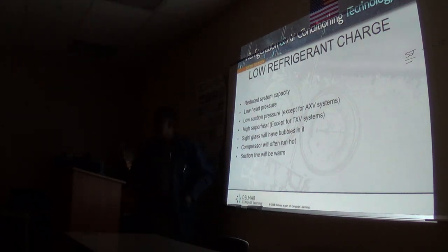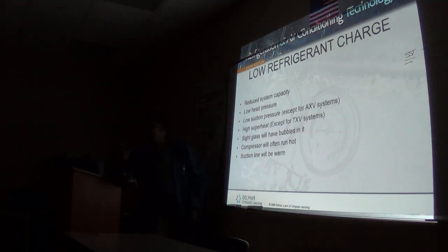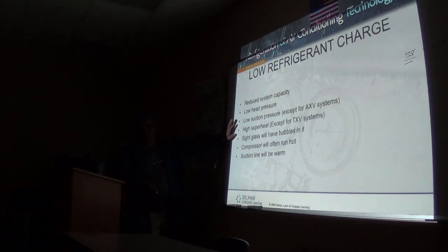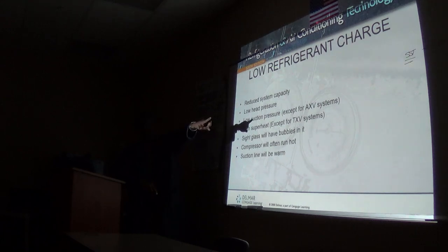So he's low on refrigerant then, right? Yeah, if all around your pressures are low, you're low on refrigerant. I have to bring him more Saturday. And of course you will have high superheat when you get low charge. Just remember that. With a negative 10, you get excessively high superheat. Subcooling is non-existent.